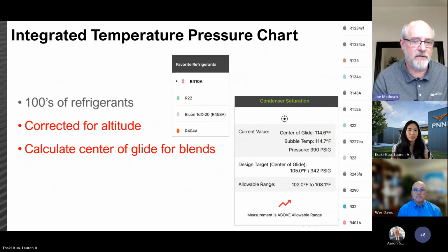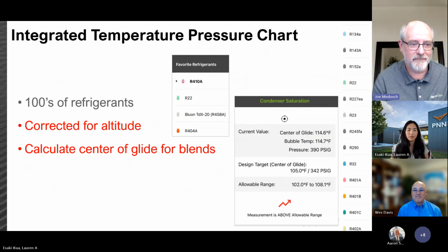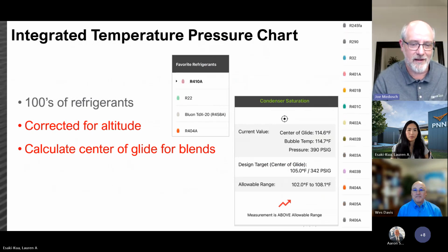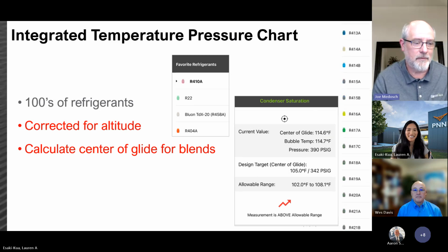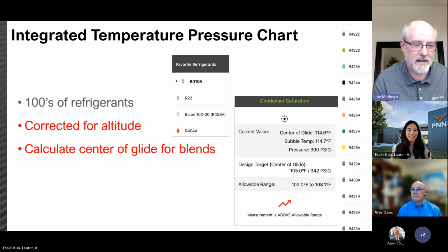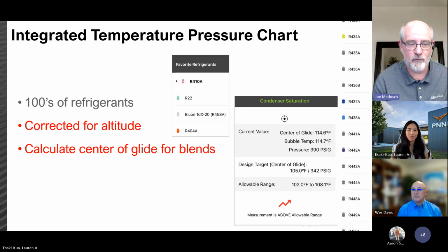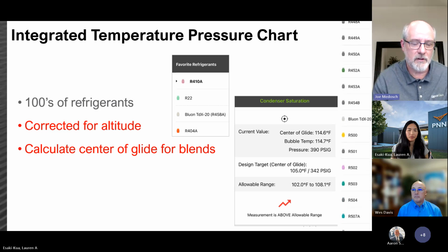So some of the other things we have, all of these refrigerants, you can see the line effect. I probably won't be able to finish talking before we get to the bottom of them. But you have to correct for altitude for these, and there's a center of glide for a blend. Like 410A is a blend, it's two different refrigerants, so you have to know what you're doing in terms of calculating that.